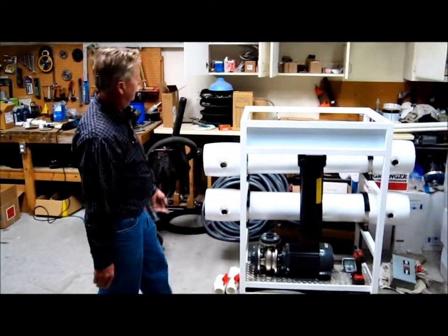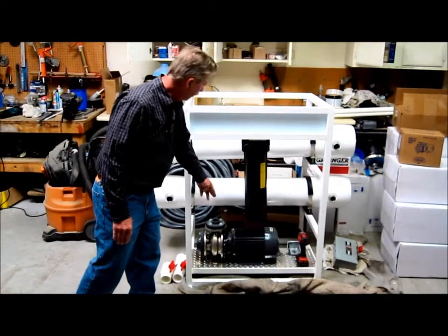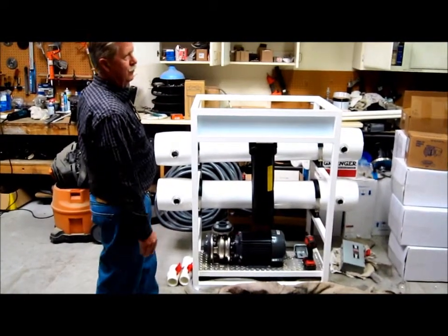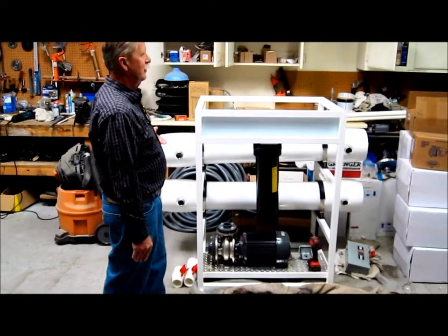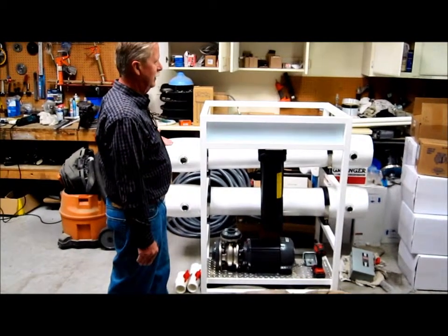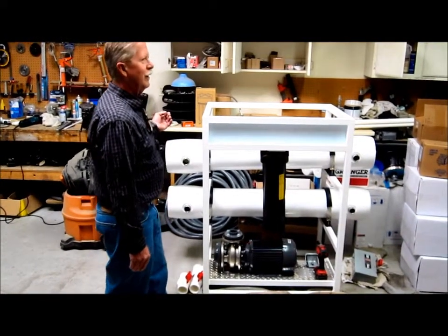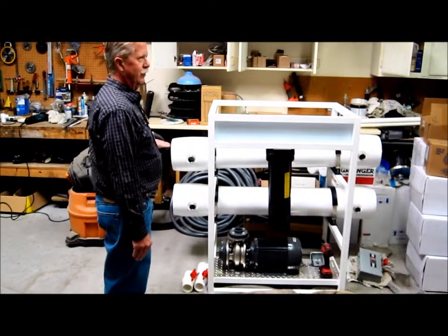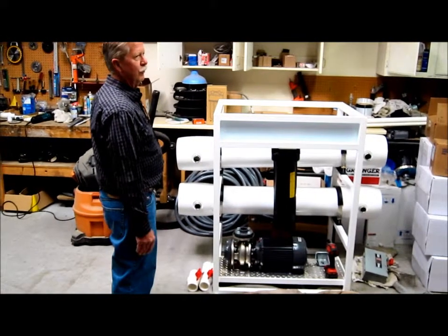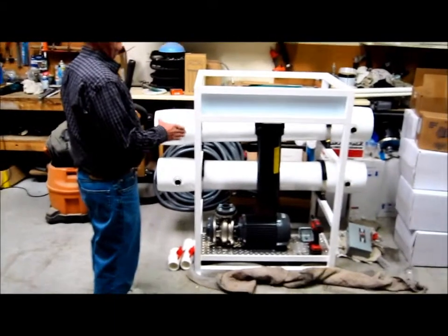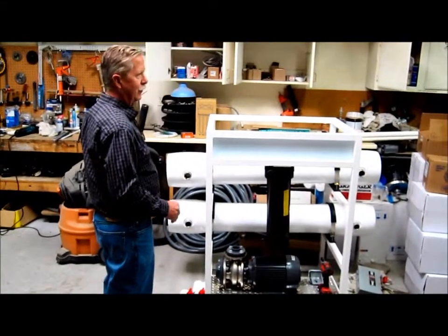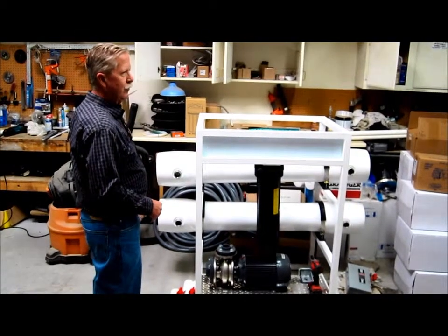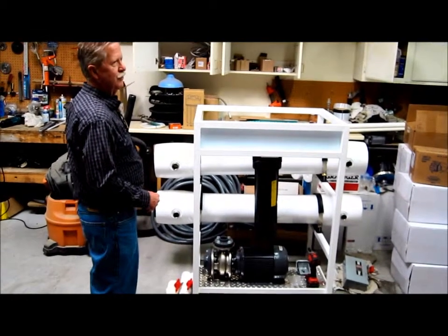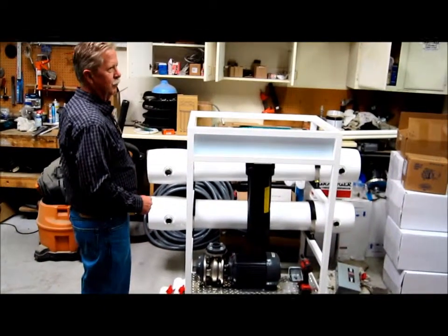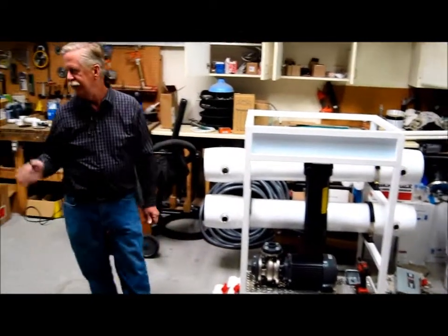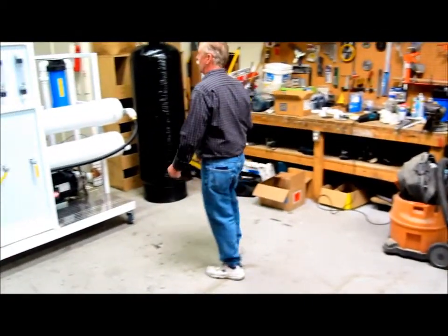You can have pre-filtration of this. It would come in through a pre-filter, which would go to a pump, go through the membranes, and then into the water storage tank. So this unit actually could easily be converted, besides for cleaning the membranes, into a system that would actually produce water, but without the delivery system. Now, a lot of companies will sell just an RO part. Now, this is just the RO without the pre-treatment and the delivery system. So, whenever you're thinking about doing a water project, you need to make sure you're getting everything you need as a complete system. Now, getting back over to this system, it all comes pre-wired.